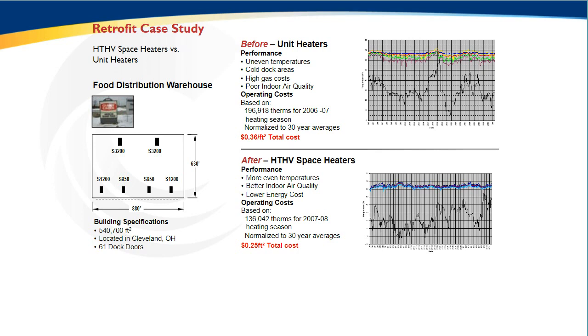that tenant had very uneven temperatures, very cold dock doors, very poor indoor air quality, such that there was no mechanical ventilation in this space. So this space was primarily ventilated through natural infiltration and operable dock doors.